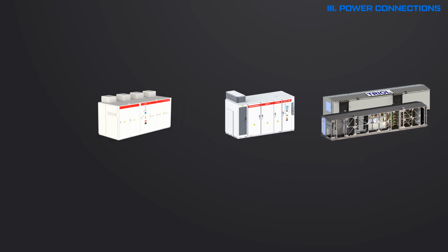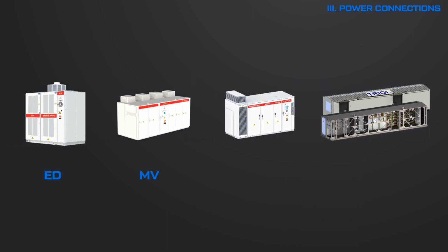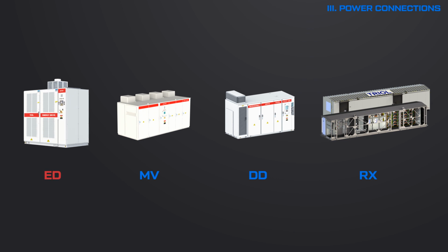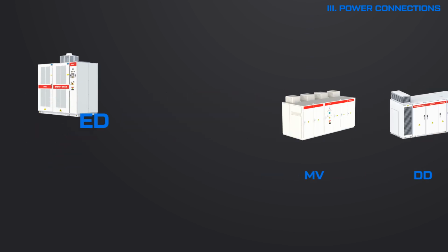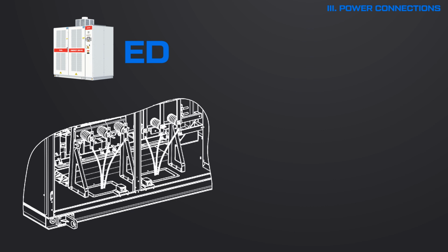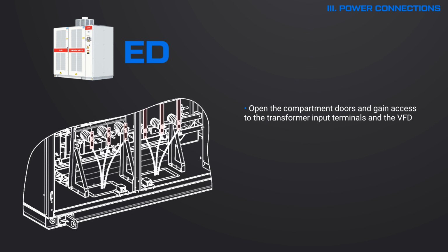Power connections. Depending on the AT27 model, there are structural differences in the input compartments which impose a number of features associated with the implementation of the power input and output cable connections. In the input compartment of the AT27 ED line, the input power cable and the motor power cable are connected in the following sequence.